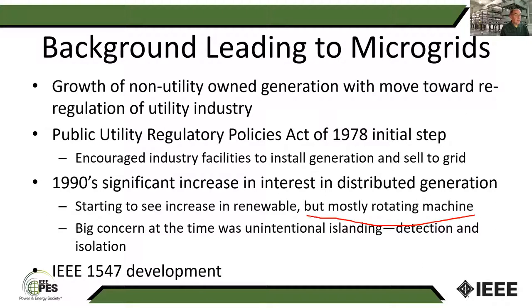One of the big concerns initially was unintentional islanding. If you had a distribution system where somebody put in a fairly large gas generator or diesel generator, and the main connection to the grid at the distribution substation opened, or a recloser somewhere along the feeder opened, and this generator happened to be able to approximately support the local load, it might not trip. And so if line crews came to work on the system, or even just loads that were frequency sensitive, the frequency would not be regulated very well, and it was possible to damage end user equipment.